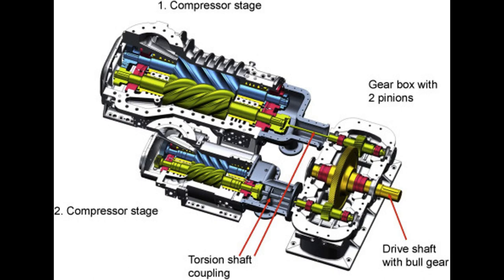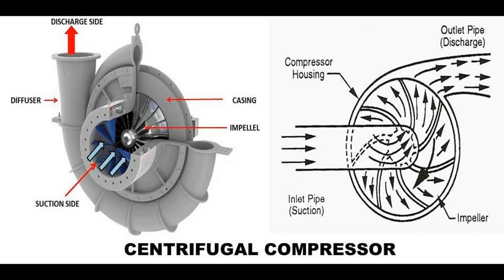The centrifugal compressor is usually used in large-capacity refrigerating systems. In this compressor, the vapour is moved in a circular motion known as centrifugal force. An impeller — a disc with radial blades — spins rapidly inside the housing, causing the gas to gain velocity. A diffuser converts this velocity energy into pressure energy, which is then discharged into the condenser. Pumping efficiency increases with speed, so centrifugal compressors are designed to operate at high speed. The main advantage is that there are no valves, pistons, or cylinders; the only wearing parts requiring attention are the main bearings.